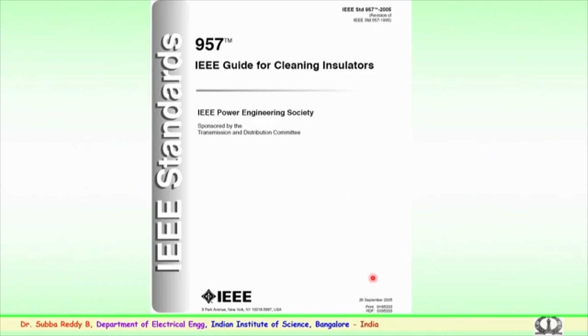So, this provides very useful information to the utilities and the people who are supplying power to consumers, to take suitable necessary action, particularly in winter conditions or ice fog conditions, and see that the cleaning of insulators is done, so that the flashovers or blackouts which happen during contamination, rainy conditions or due to fog can be reduced. With this intention, the IEEE guide for cleaning insulators has been framed, very important information for the utilities as mentioned.